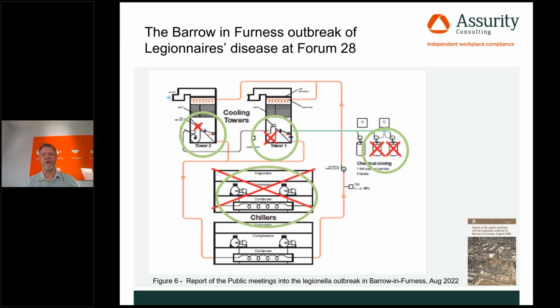So regardless, from a management perspective, this system was in poor condition. Why was it never flagged? Over the last 30 years I've had 4 occasions where, having looked at an installation, I've turned it off because there were serious concerns, and at least 2 of those related to no form of chemical treatment at all going into the system. I must admit, if I'd looked at this one in this condition, it probably would have been my 5th.